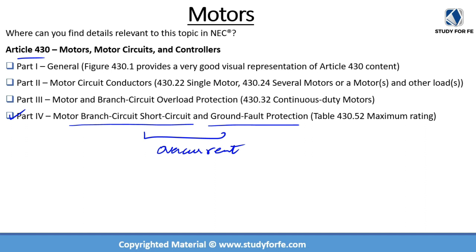Part 4 of Article 430 is titled Motor Branch Circuit, Short Circuit and Ground Fault Protection — basically overcurrent protection. The most important content in Part 4 is Table 430.52, which provides the maximum rating or setting of Motor Branch Circuit, Short Circuit and Ground Fault Protective Devices. Using this table, you can identify your scenario — single phase motor, multi-phase motor, squirrel cage, synchronous, or wound rotor motor — and whether you're using non-time delay fuses, time delay fuses, instantaneous trip breaker, or inverse time breaker. Part 3 deals with overload conditions; Part 4 deals with overcurrent situations including short circuit and ground fault.